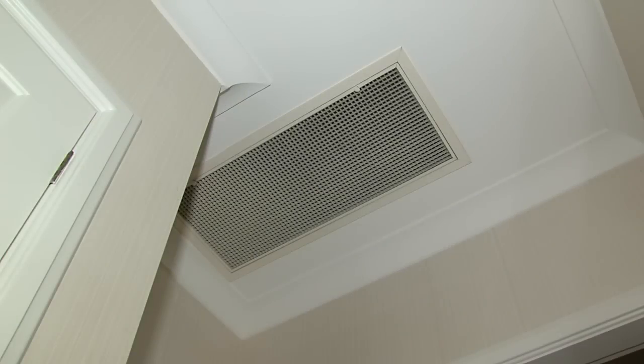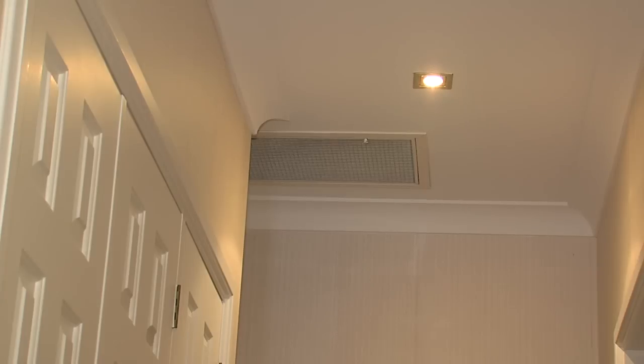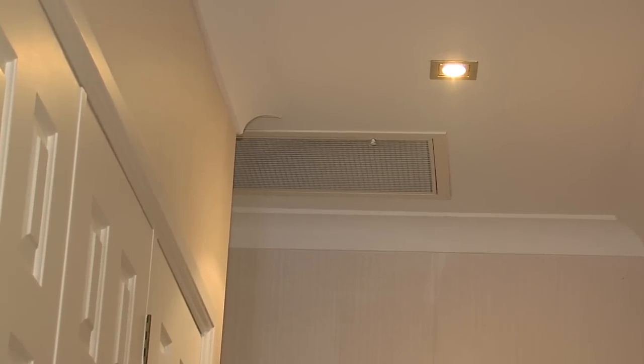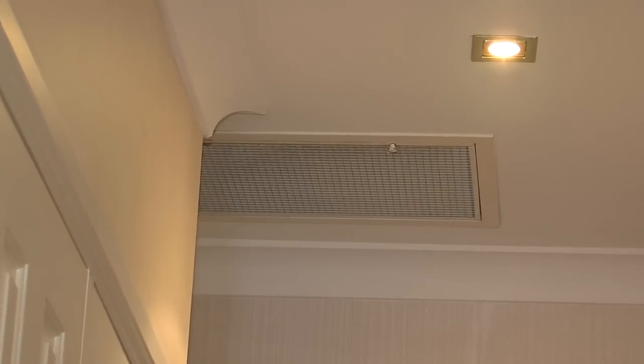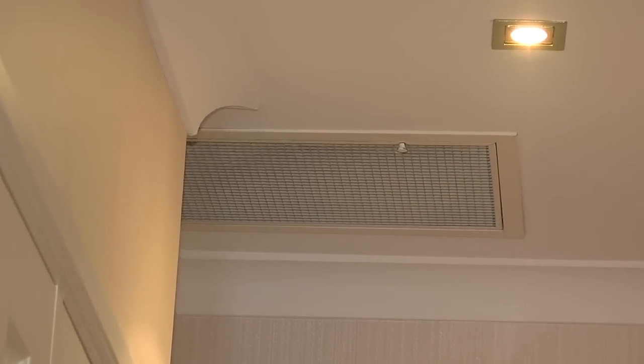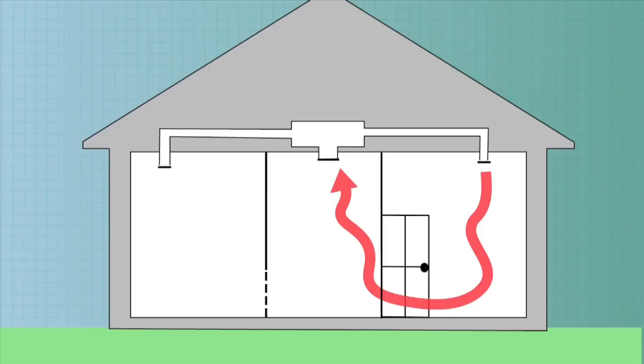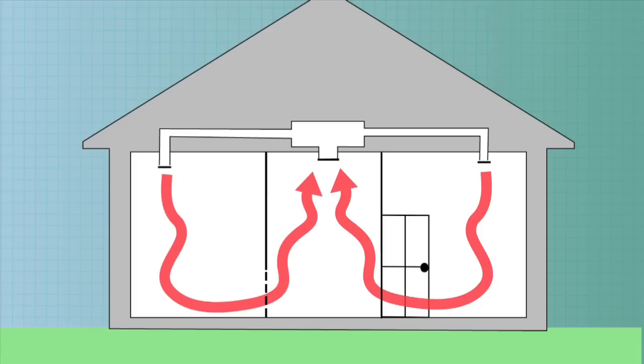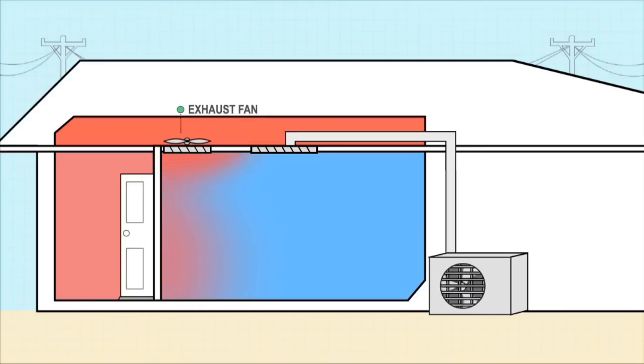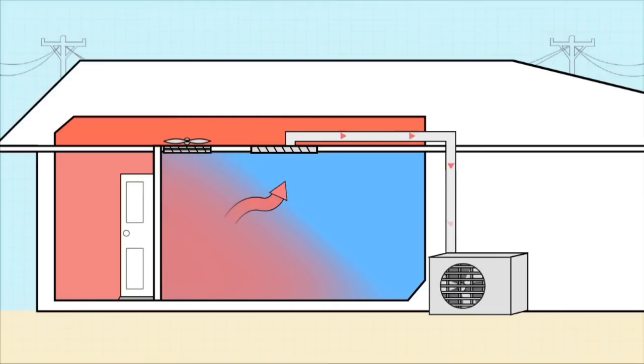The return air grill is typically located in the ceiling of a hallway or entrance space to ensure maximum air circulation from supply vents. Ensure conditioned systems allow air to flow back to the return air grill by leaving doors open when in use or by installing grills in the doors or walls. Eliminate unwanted draughts from the circulation system by installing backdraft dampers on exhaust fans and sealing off unconditioned spaces.